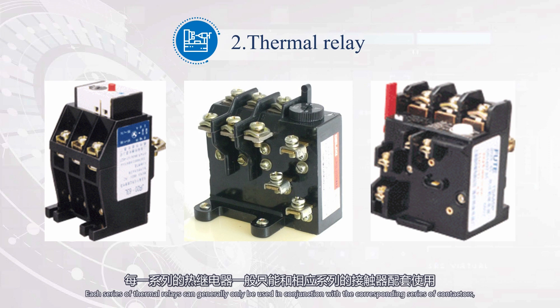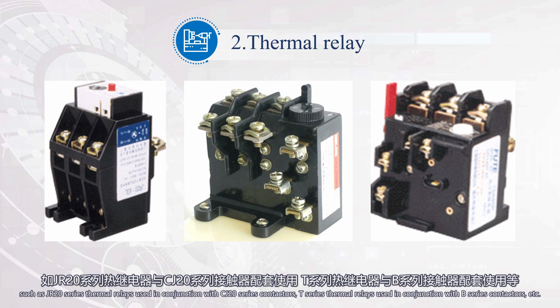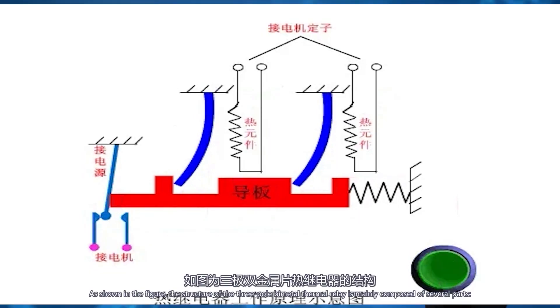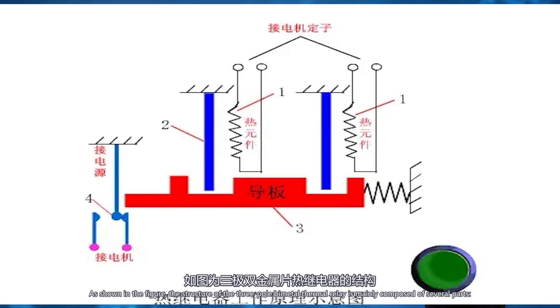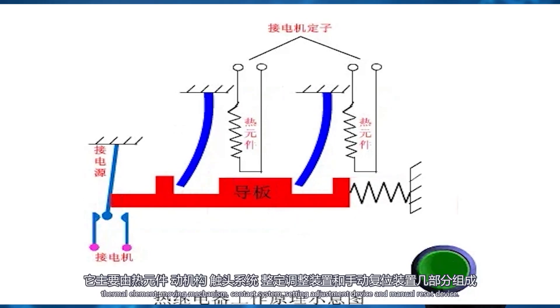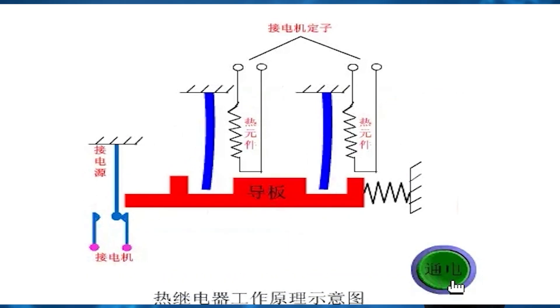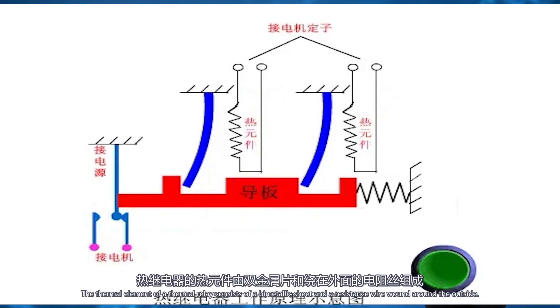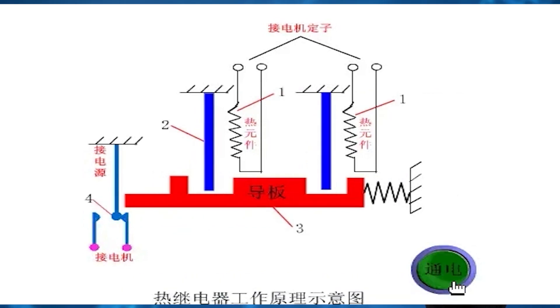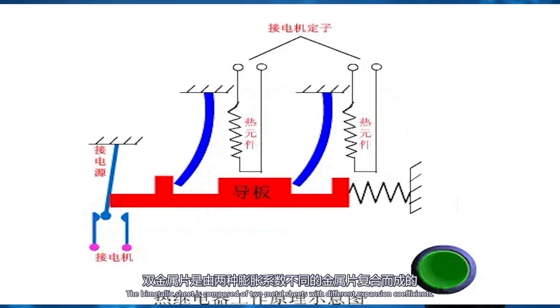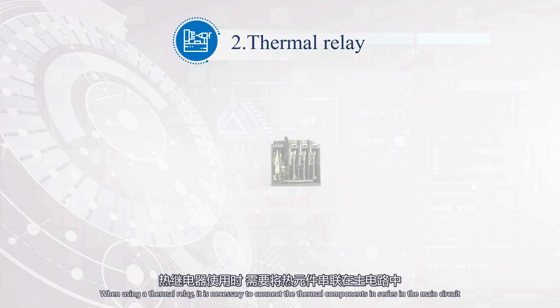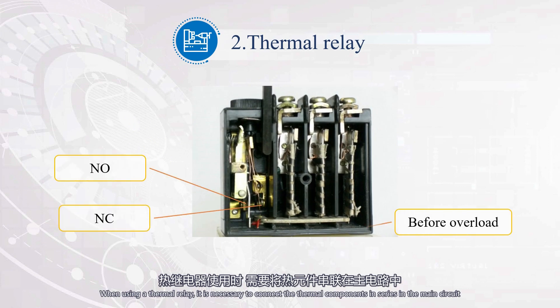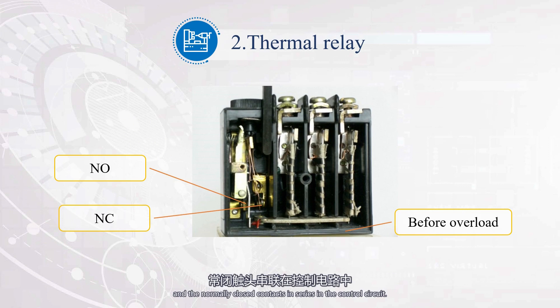Each series of thermal relays can generally only be used in conjunction with the corresponding series of contactors, such as JR20 series thermal relays used with CJ20 series contactors, and T series thermal relays used with B series contactors. The structure of the three-pole bimetallic relay is mainly composed of a thermal element, moving mechanism, contact system, setting adjustment device, and manual reset device. When using a thermal relay, the thermal components must be connected in series in the main circuit and the normally closed contacts in series in the control circuit.